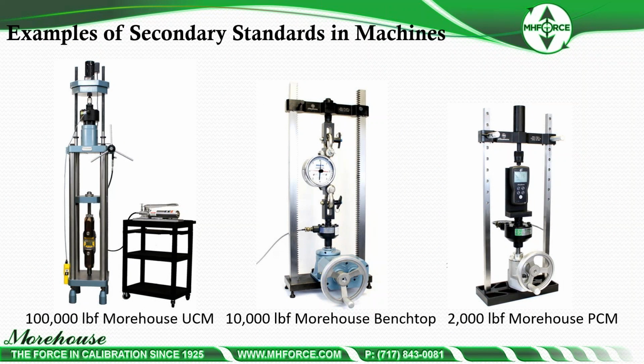Some examples of machines. All of these are Morehouse machines. We have our universal calibrating machine. Standard here, calibrated by deadweight primary standards. This one's a 100,000 pound machine. We put it in our deadweight machine. We calibrate it. This standard here can calibrate other load cells and assign a Class A range. Here is our bench top. This is a 10,000 pound machine, and it's a nice somewhat portable unit. The weight is around 150 pounds, but it can be sat on a bench top. It can be rolled around. And then we do have a portable unit, which is our little, smaller 2,000 pound Morehouse PCM.